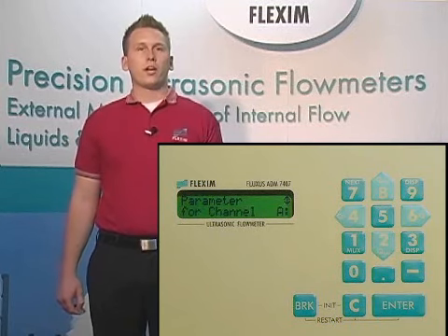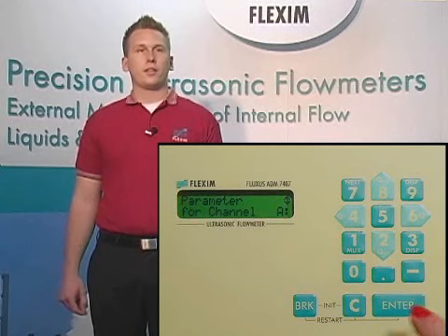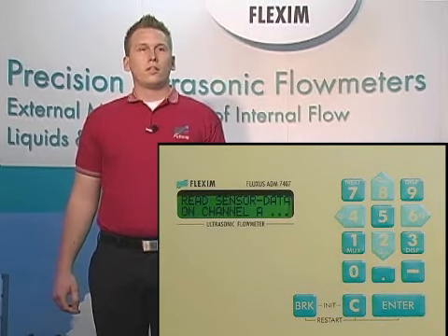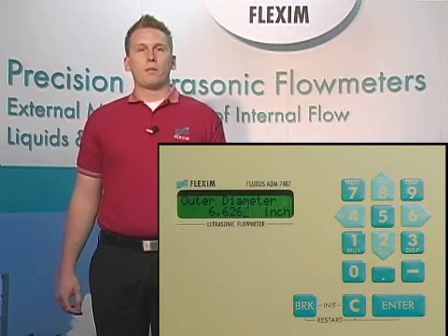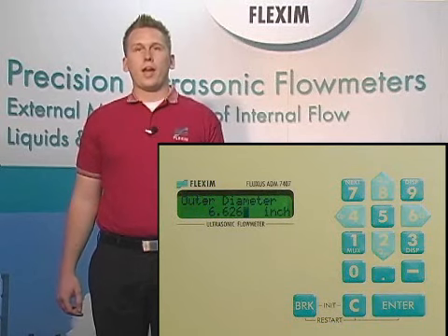Now we're going to select channel A by scrolling up and down, then hit enter. Now we need to enter the outer diameter of our pipe. Be careful here to enter the actual outer diameter and not the nominal dimension.